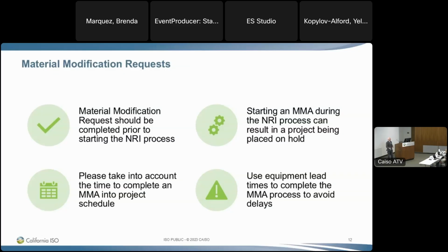So it's very important that the MMA is completed prior to beginning the NRI process. If you do have to start an MMA during the NRI process, depending on the change, it could result in the project being placed on hold until the equipment is approved. So if you're changing inverters, transformers, or gen-tie items, that can result in the project being placed on hold until that equipment is approved. We want to make sure you're taking into account the time it takes to complete the MMA in your project schedule. That's something you'd need to work with queue management on, or your own interconnection group, to make sure they're aware these changes need to be submitted prior to starting the NRI process.